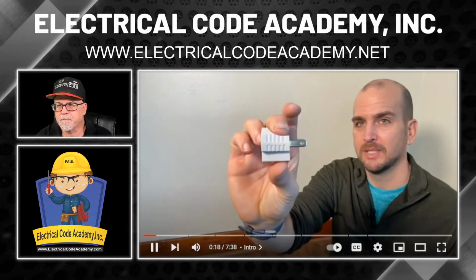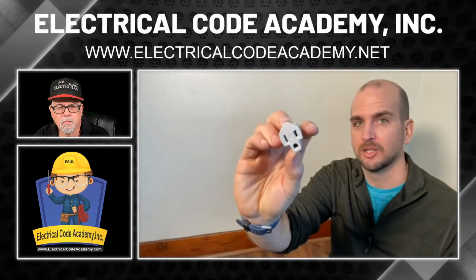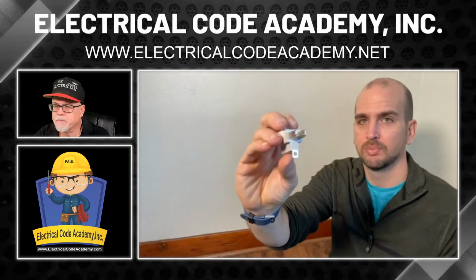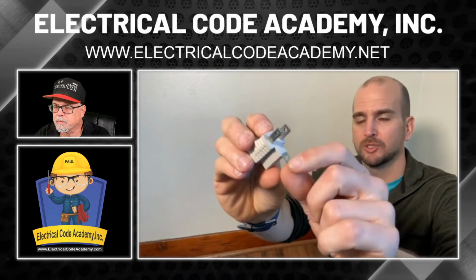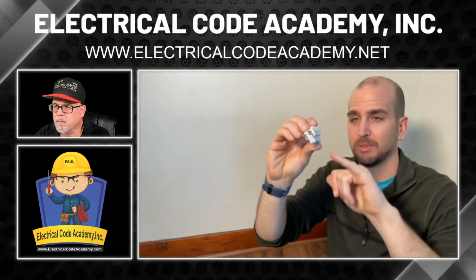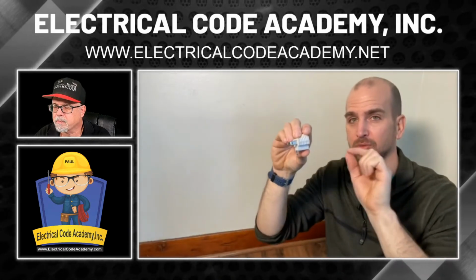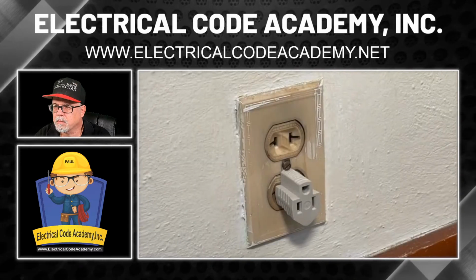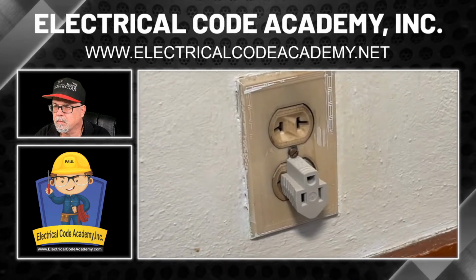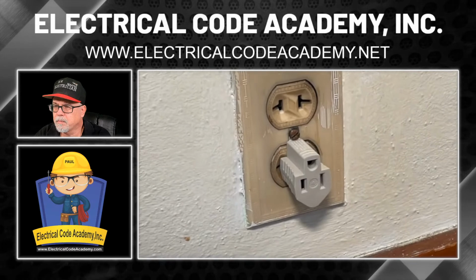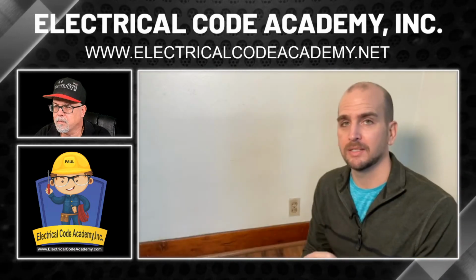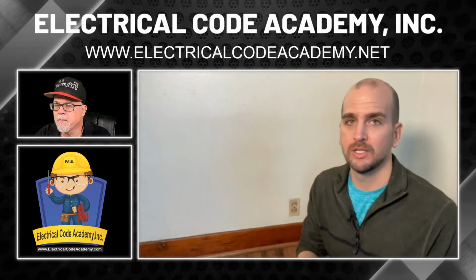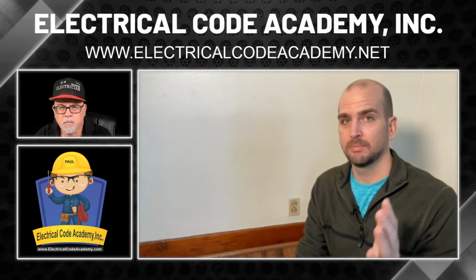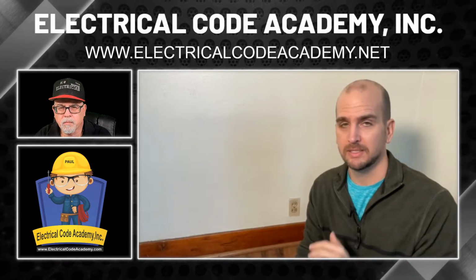To solve that, you might be using one of these adapters that takes a 3-prong and gives you that 2-prong, and it has an additional small strap here that actually some people screw in. So the screw for the faceplate right in the center here, they'd screw that in. Now that's not creating a ground because there is no equipment ground coming to this box. So it's just an unsafe way to do it. So let's get you upgraded to a 3-prong and do that safely.